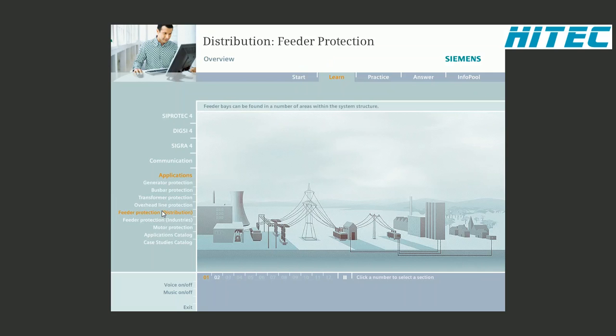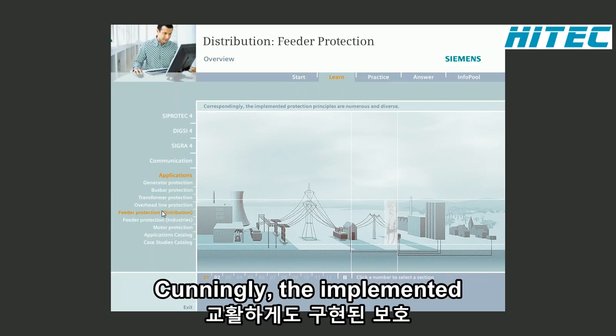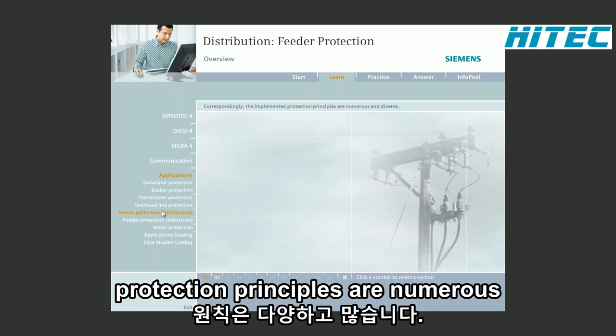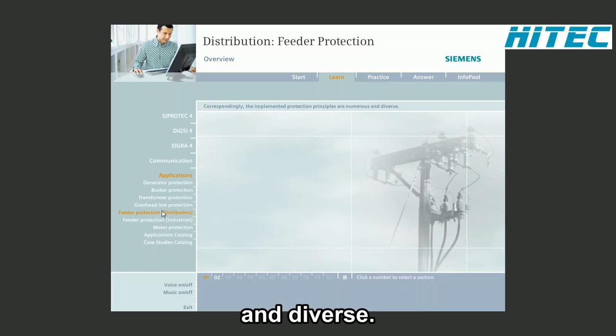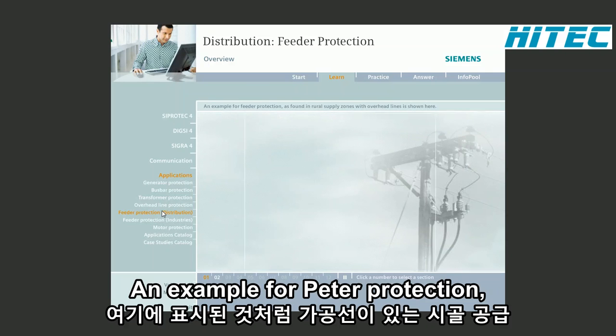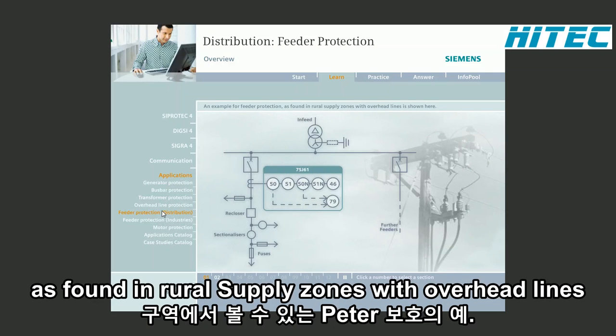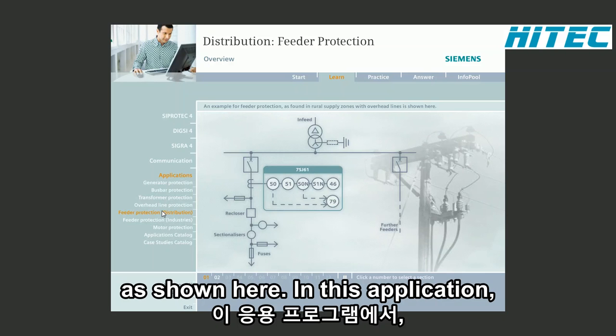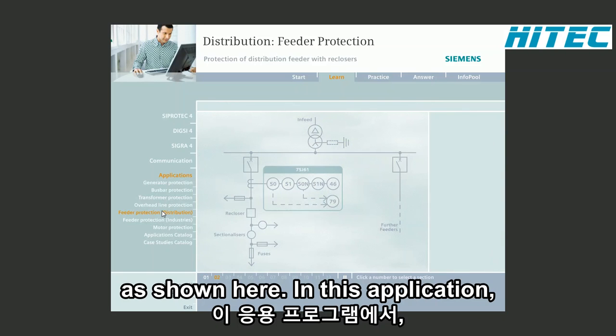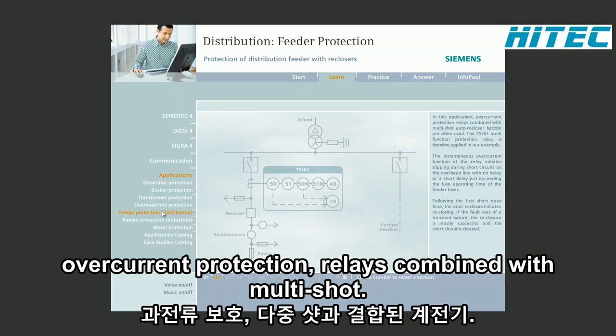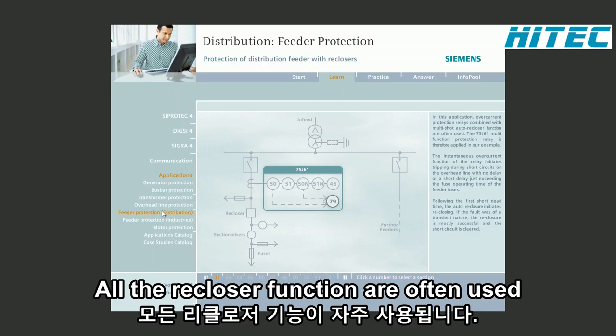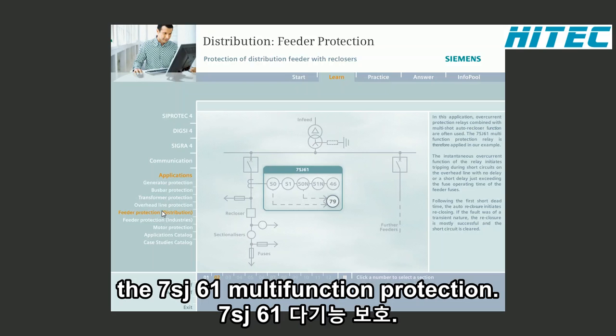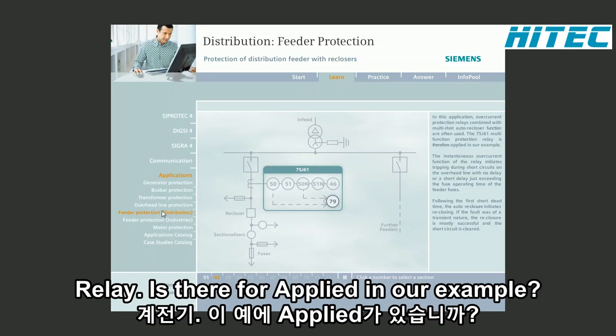Feeder bays can be found in a number of areas within the system structure. Correspondingly, the implemented protection principles are numerous and diverse. An example for feeder protection, as found in rural supply zones with overhead lines, is shown here. In this application, overcurrent protection relays combined with multi-shot auto-recloser function are often used. The 7SJ61 multifunction protection relay is therefore applied in our example.